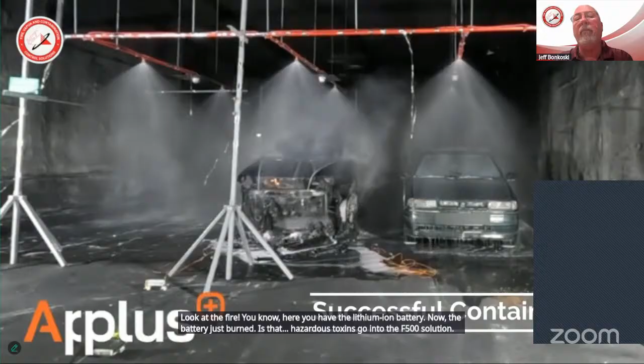When they designed the test, it wasn't expecting to see the fire extinguished. They wanted to see if they could control the fire until first responders could arrive on scene and extinguish it. But they saw great success, exceeding expectations. There was no fire spread, and by the end of 60 minutes, the fire was extinguished, even though that wasn't the system's intended purpose. So the system was even more effective than they thought it would be.